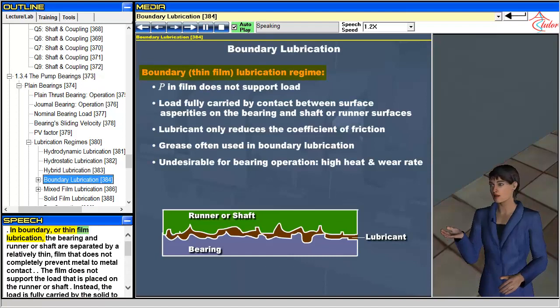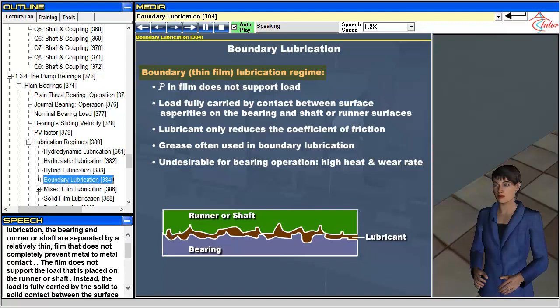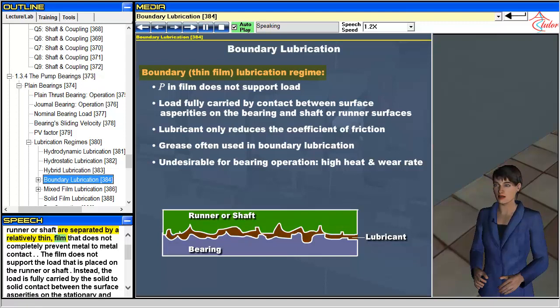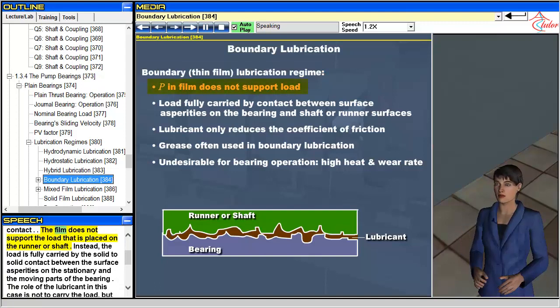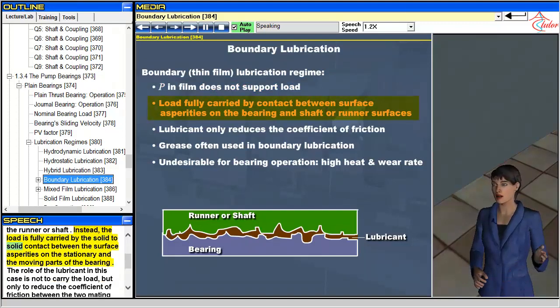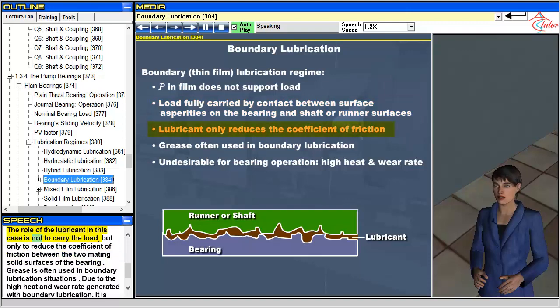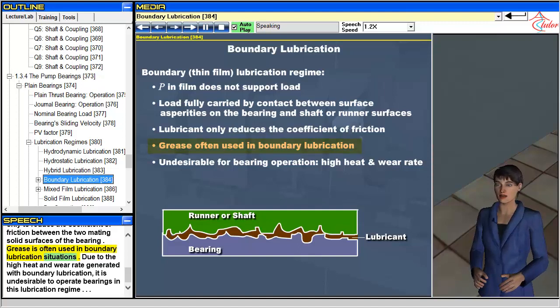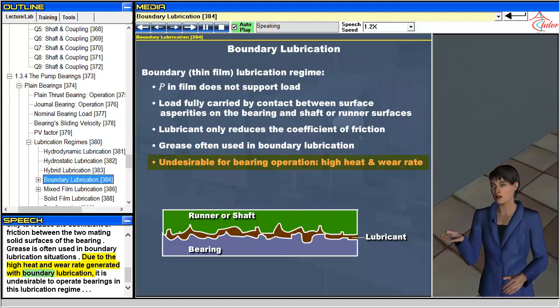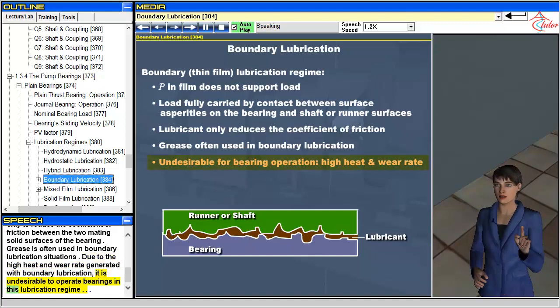In boundary or thin film lubrication, the bearing and runner or shaft are separated by a relatively thin film that does not completely prevent metal-to-metal contact. The film does not support the load; instead, the load is fully carried by solid-to-solid contact between the surface asperities on the stationary and moving parts of the bearing. The role of the lubricant is only to reduce the coefficient of friction between the two mating surfaces. Grease is often used in boundary lubrication situations. Due to the high heat and wear rate generated, it is undesirable to operate bearings in this regime.